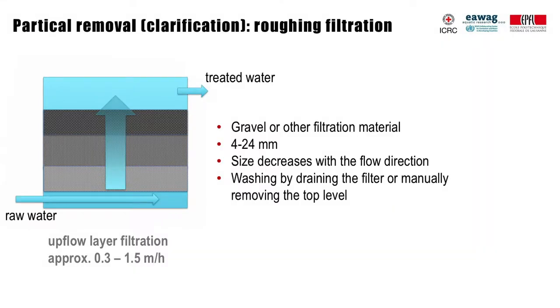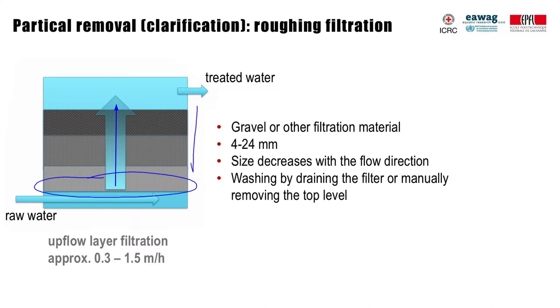For rather turbid waters, roughing filters can be used prior to rapid or slow sand filtration or disinfection. Differently sized coarse material is used in roughing filters, and the size decreases in the direction of flow. There are different configurations — upflow, downflow or horizontal flow. In an upflow filter, water moves from bottom to top and the retained solids accumulate predominantly at the bottom of the filter. They can be flushed out by reversing the flow or simply draining the filter.